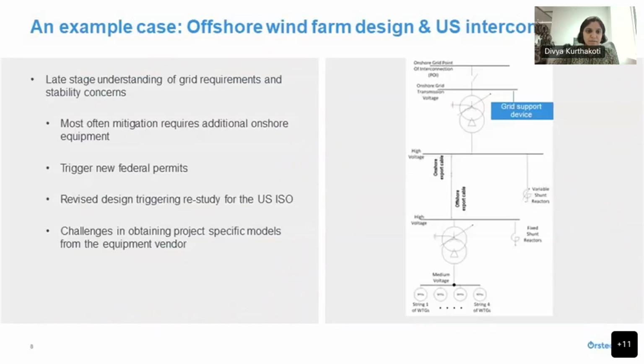From a design perspective, just going by the engineering, I think the grid support device needed would be very different. Most often, to mitigate issues with meeting grid requirements or TO requirements, we use a grid support device because of the distance we are electrically from the ocean. We have multiple transformer stages, export cables, and it's very hard to control the reactive power flows, and sometimes the short circuit could be a challenge.